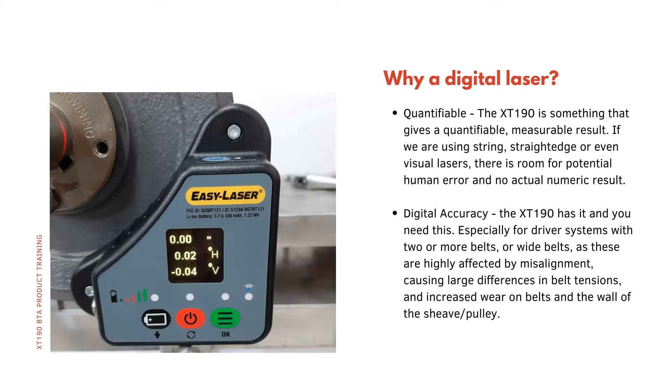The third factor is that it's quantifiable. The XT190 gives a quantifiable, measurable result. If we are using string, straight edge or even visual lasers, there is room for potential human error and no actual numeric result is given. The fourth is digital accuracy. The XT190 has it, and you need this — especially for driver systems with two or more belts or wide belts, as these are highly affected by misalignment, causing large differences in belt tensions and increased wear on belts and the wall of the sheave or pulley.